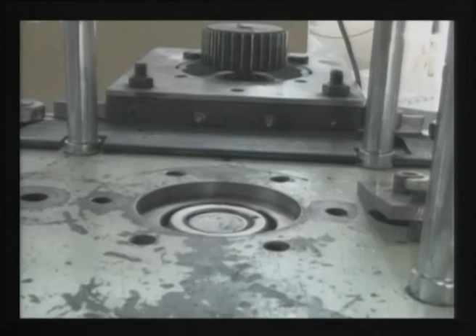Now I am showing how this reciprocating motion is provided to the Teflon piston inside the medium cylinder. See, this piston is reciprocating inside this medium cylinder at the bottom. This is the bottom medium cylinder. Now the piston is given reciprocating motion in the top medium cylinder also. And the reciprocating motion of these 2 pistons is synchronized by a limit switch. The change of direction of the piston is controlled by the limit switch. See how this limit switch is activated now, and after this activation the direction of the piston is reversed.